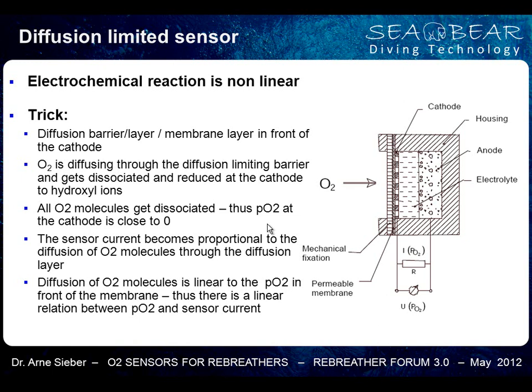So what we achieve with this is that the sensor current becomes proportional to the diffusion of oxygen molecules through the diffusion layer. This is now a mechanism that only depends on a diffusion law. So it's not an electrochemical process anymore. The diffusion of oxygen molecules is now linear to the PO2 in front of the membrane, and there is a linear relation between the PO2 and the sensor current. So with this type of sensor assembly, we get a linearization of the output signal.